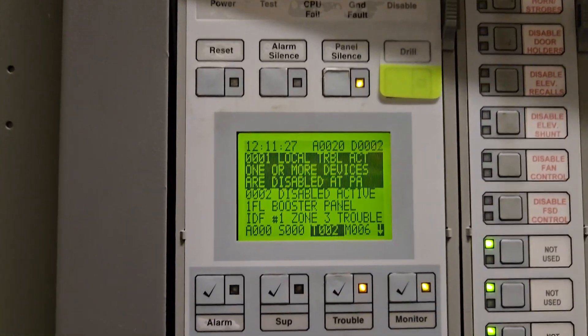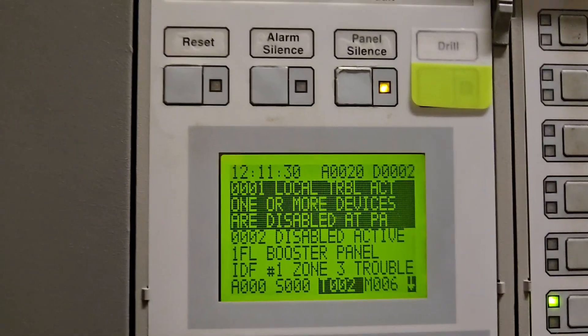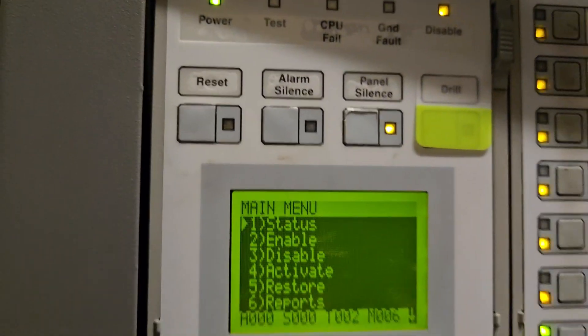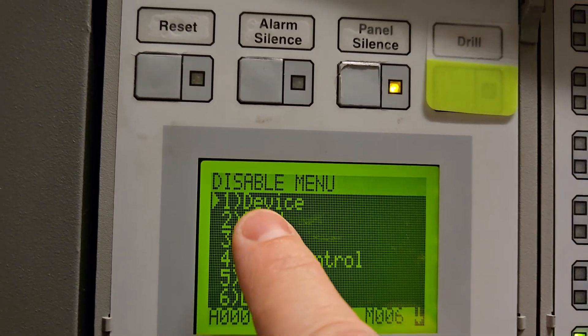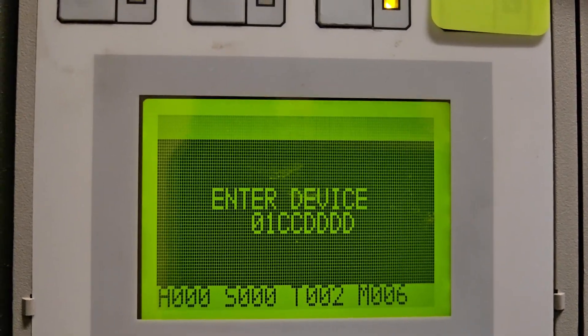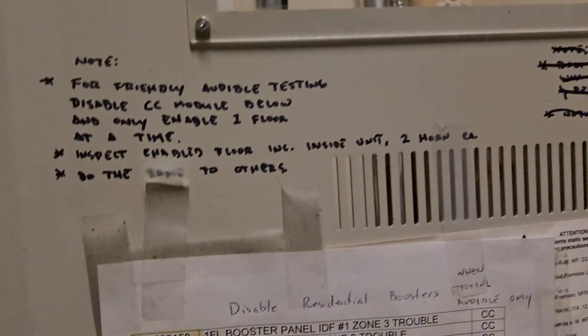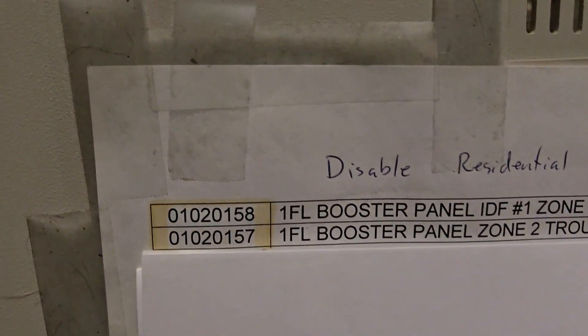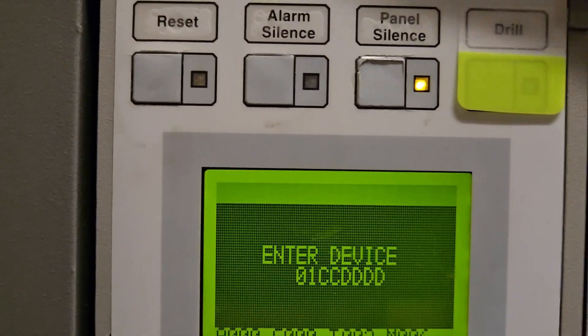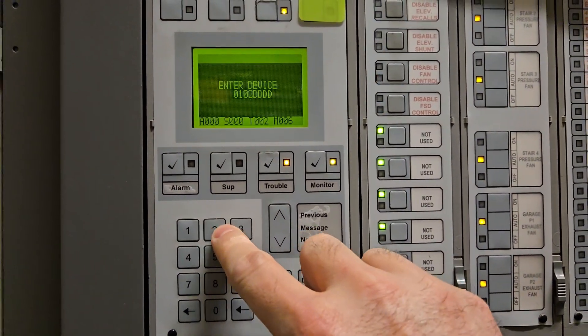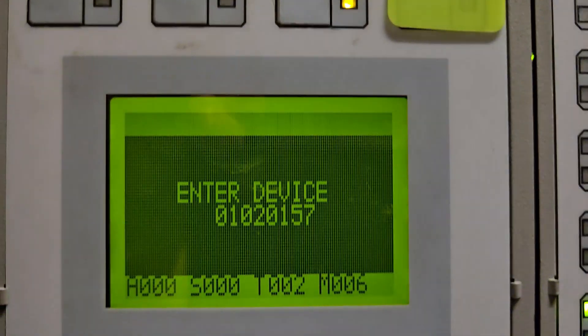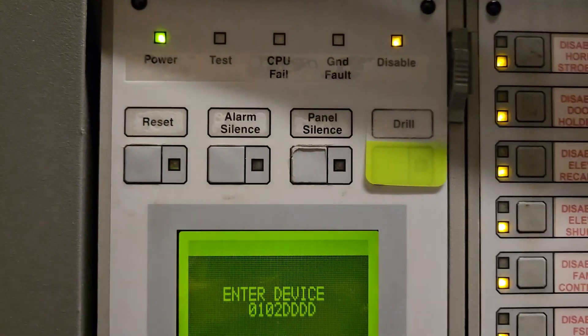Now I'm going to put in the other four troubles so we have all of floor one's horn strobes isolated. I'll go command menu, hit number three for disable, hit number one for device. The eight-digit number starts with zero one again. The second one is 01-02-0157, so I already have zero one and I'll put in zero two, zero one, five seven. I hit enter, get another trouble — now I'm up to three troubles.